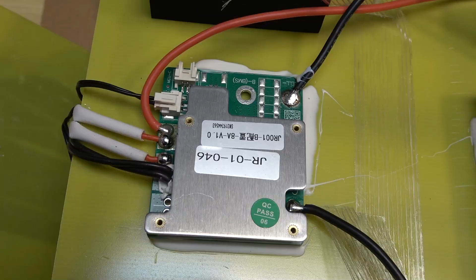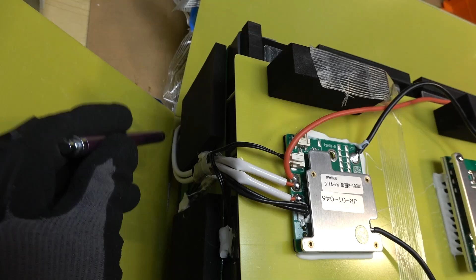Next to the BMS, we have another circuit board, and this is the control for the heating pad. On this board, we've got a red wire which comes from the main positive terminal of the battery, and then 2 wires that output to the heating pad on the bottom of the battery, and the output of this heating pad is controlled by this board.